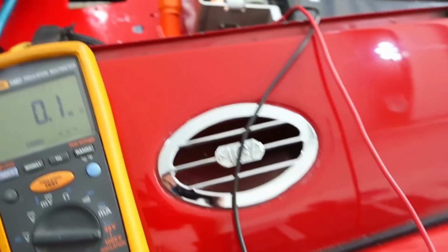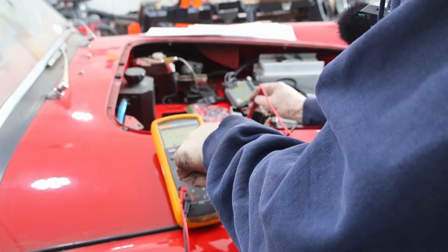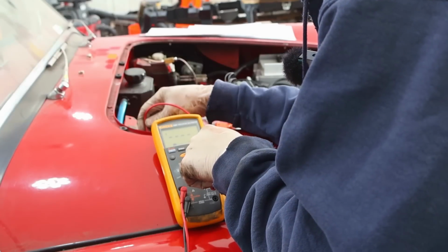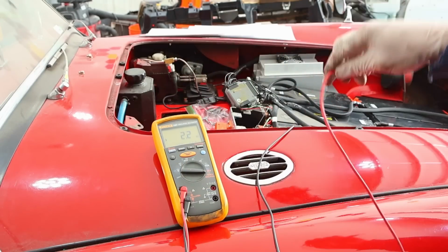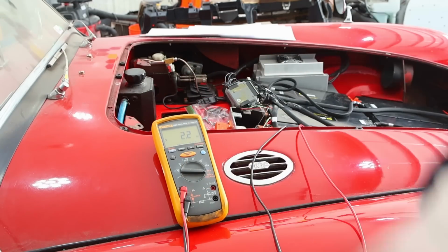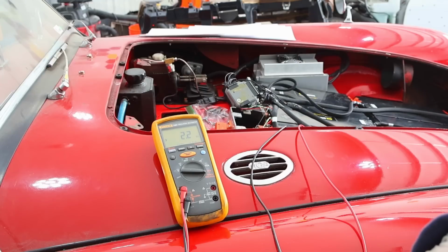So I don't know if you can tell, but right there we've disconnected one cable, and back there we've disconnected another. Let's try this again: 2.2 giga ohms, 1.8, 2.2 giga ohms. So without those cables connected, we have great isolation. The problem seems to happen only when those cables are connected to the high voltage junction box, which makes me believe the issue is happening within the box itself.